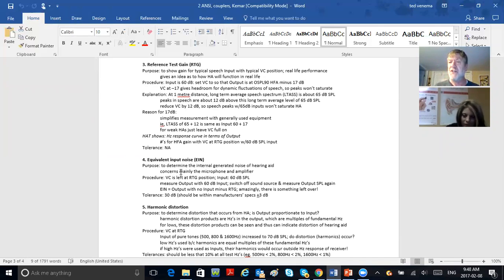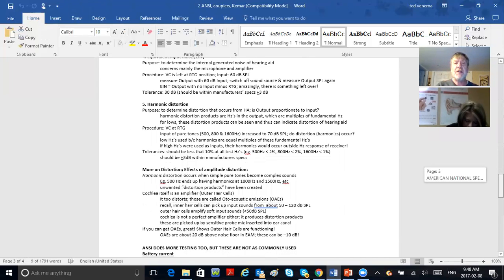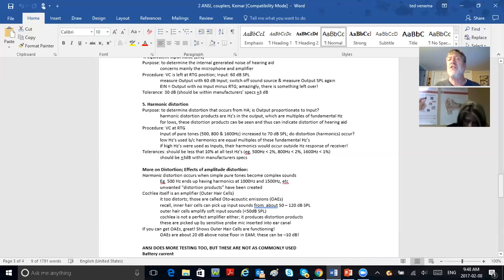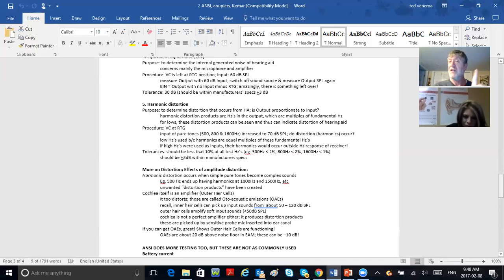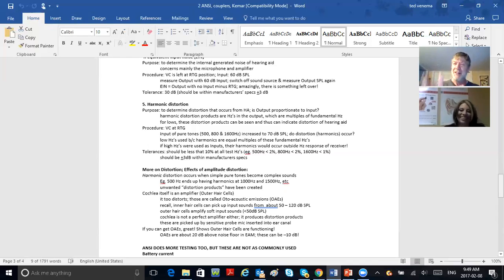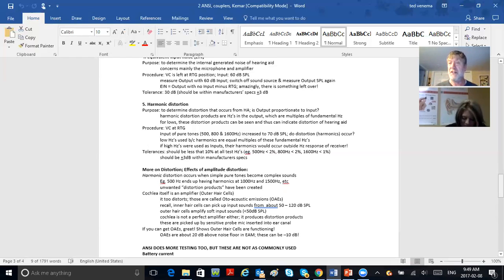The last test we really care about is harmonic distortion. That's not the noise inside the hearing aid—now you're looking at how much the hearing aid is distorting the sound. If you put a 500 Hz tone into the hearing aid, is only a 500 Hz tone coming out, or are harmonics of 500 Hz also coming out? In other words, when you invited Mary to the party, did Mary bring her kids along?